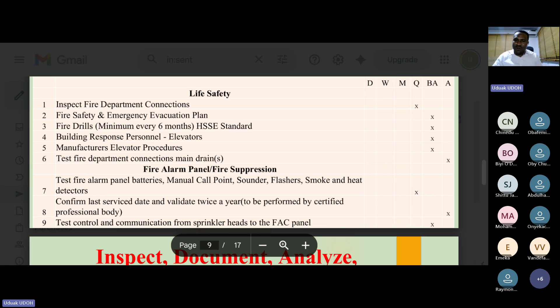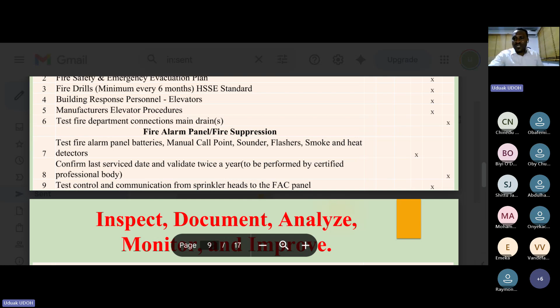Should you have any of these equipment or assets on your site, they will come to your site and undergo this test with you. But it's always good for you to do it once every year, right? And that's always best. Then we have the fire alarm panel and fire suppression. So we should always test the fire alarm panel batteries, the manual call points, the sounders, the flasher, the smoke and heat detectors. We should always do that every quarter. Yes, every quarter, every 3 months.